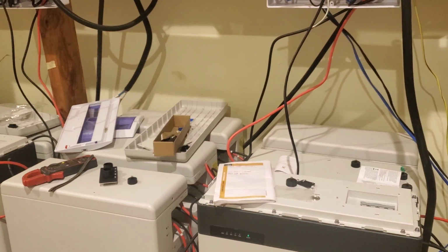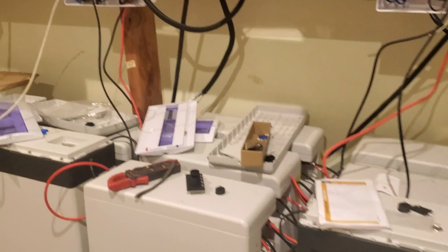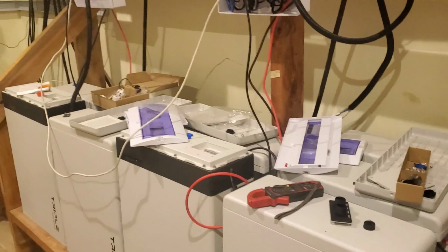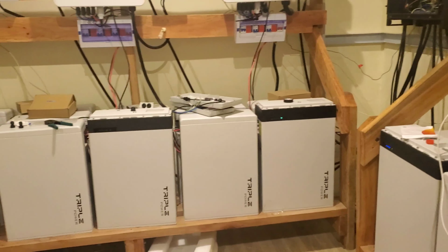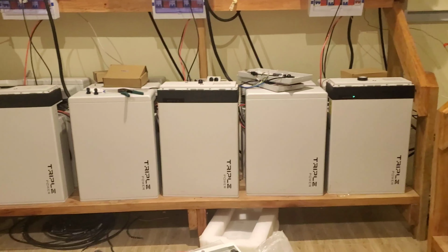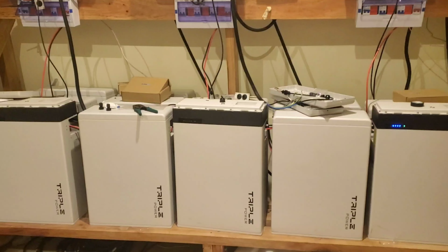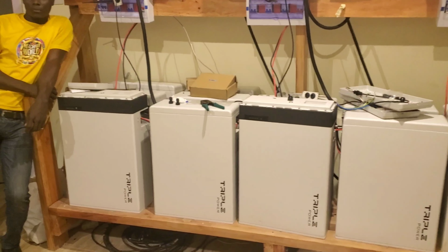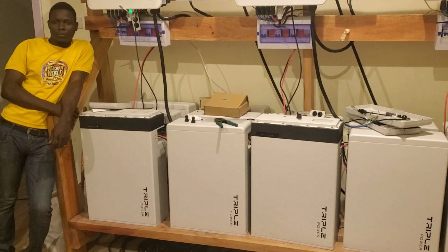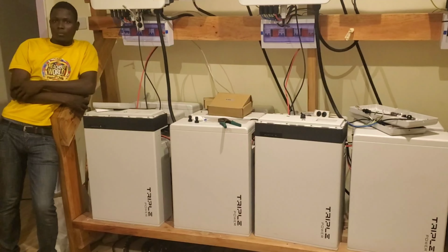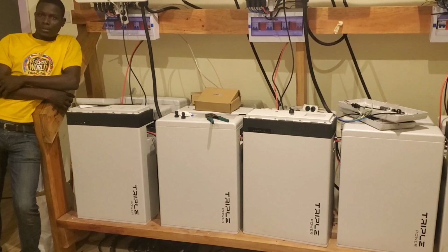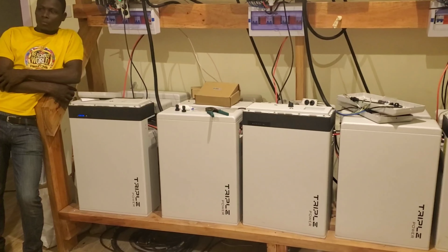Now I'm thinking, since we are going to take 2 inverters offline, we can add those batteries back on them. Those batteries are now fully charged, right? Is this one charged? So all the batteries are now 100% charged. What we'll do is remove the interconnecting cables from the inverters that are not currently working, and then we'll do our 4, 4, 4, and 4. How many inverters in total? 10 inverters, times 4 batteries. So that's 40 batteries instead of 48.